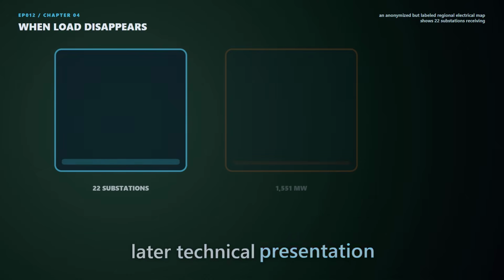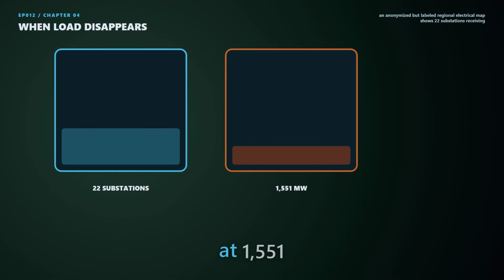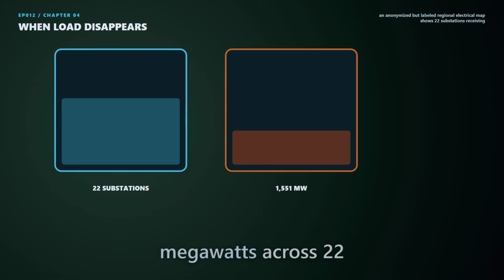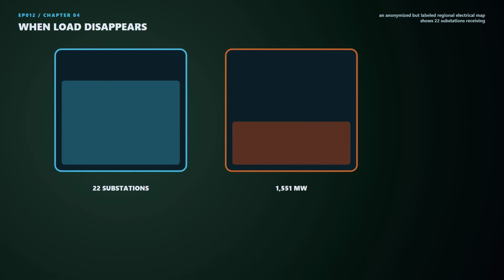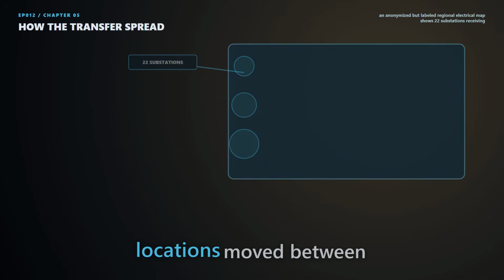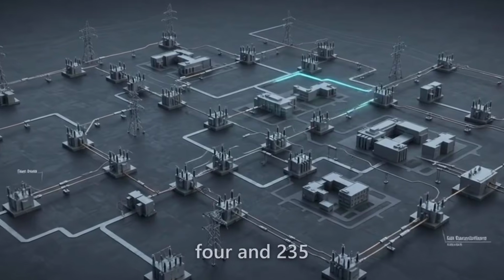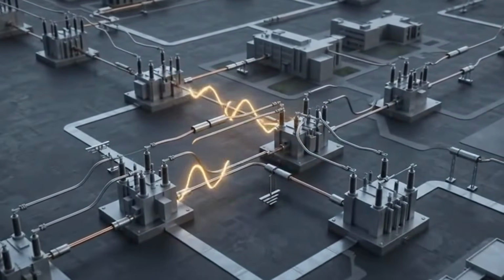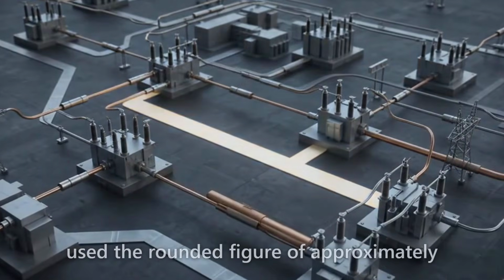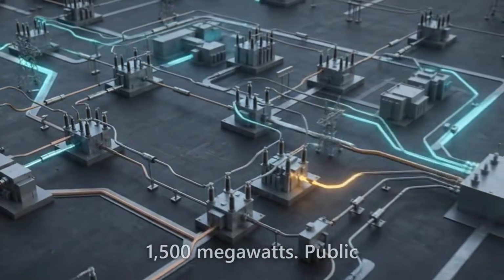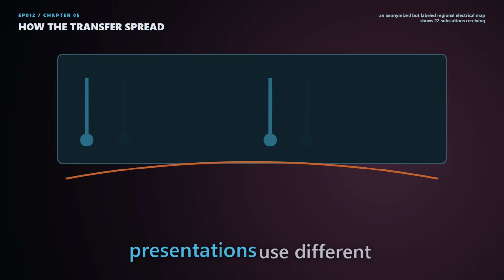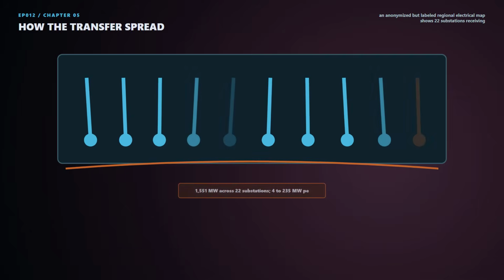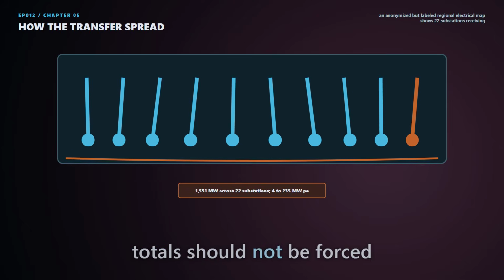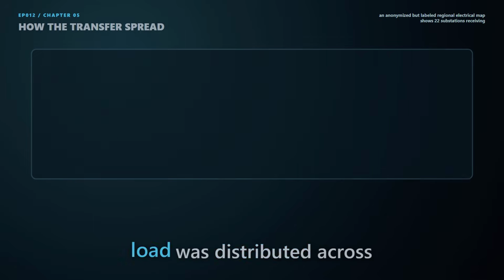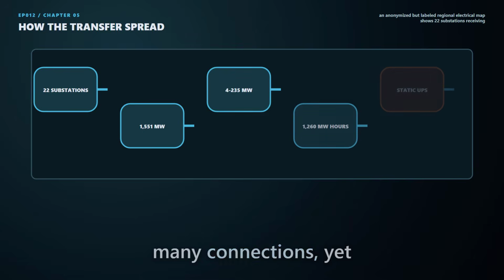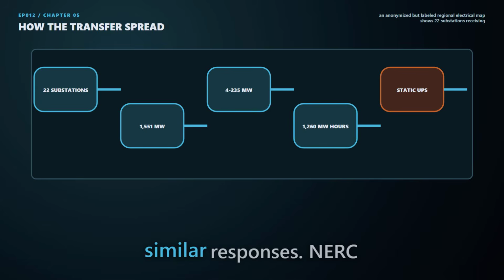Dominion's later technical presentation put the July transfer at 1,551 megawatts across 22 substations in the area it analyzed. Individual locations moved between 4 and 235 megawatts, with an average of 70.5. NERC used the rounded figure of approximately 1,500 megawatts. Public presentations use different counting scopes for substations and load points, so those totals should not be forced into false precision. The load was distributed across many connections, yet the same disturbance triggered similar responses.